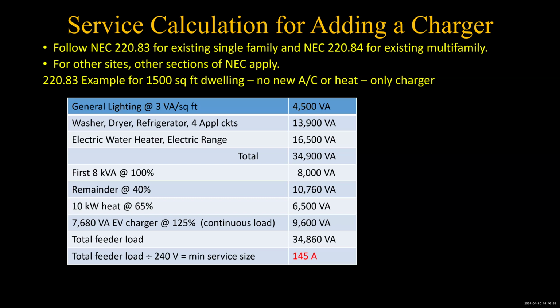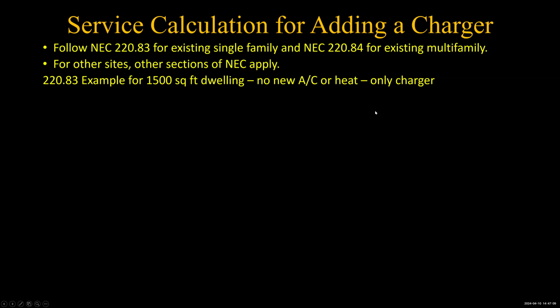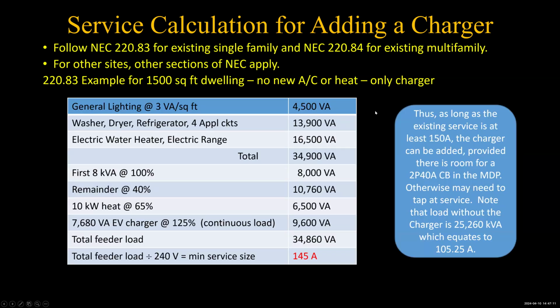And then you get a total feeder load of 34,860 volt amperes. And divide that by 240 volts, 145 amps. So, pretty straightforward calculation. Whoops. And as long as your service is 150 amps, you're good to go. As long as you have a 2-pole 40 amp circuit breaker in your main distribution panel.